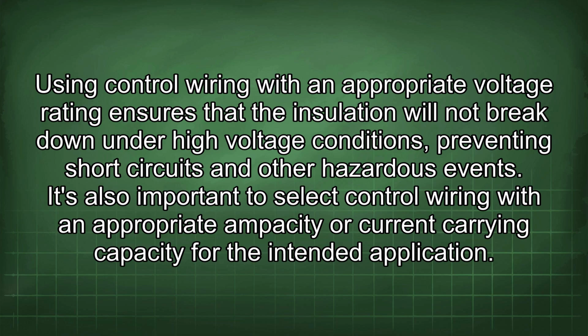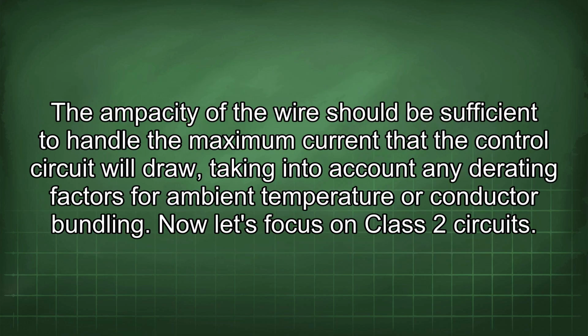It's also important to select control wiring with an appropriate ampacity, or current carrying capacity, for the intended application. The ampacity of the wire should be sufficient to handle the maximum current that the control circuit will draw, taking into account any derating factors for ambient temperature or conductor bundling.